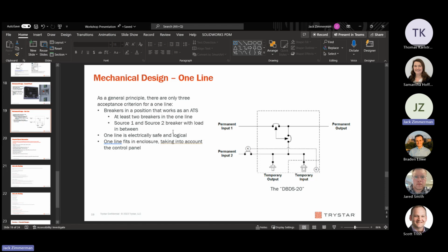As well as that, the one-line needs to be electrically safe and logical. Looking at a one-line, you wouldn't even be able to tell it's an ATS necessarily. You can ignore the fact that it's an ATS as long as these are mechanically interlocked, which it shows here. The rest just needs to be electrically safe like any other one-line, and it needs to fit in the enclosure, taking into account the control panel. As long as it's electrically safe, interlocked, and logical, you can add dual purpose and all that kind of stuff.